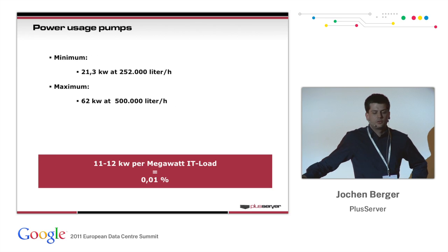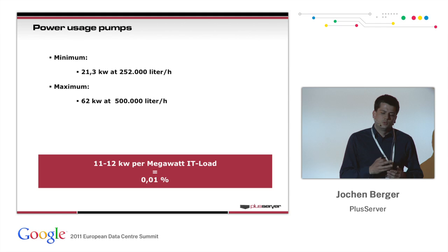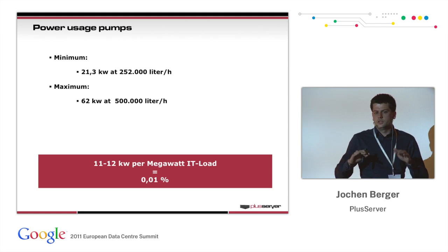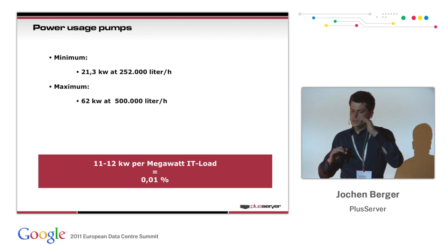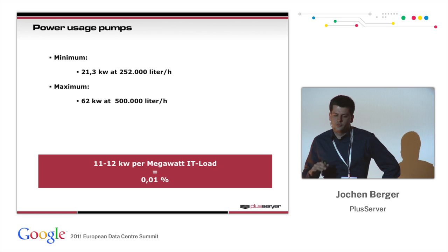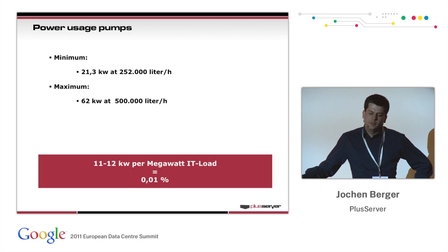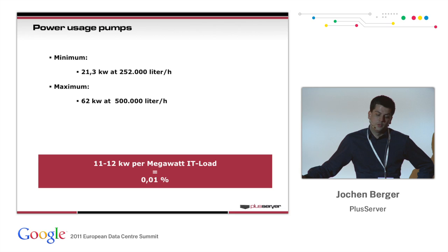Some numbers about the power usage of the pumps so that you get a feeling how much power it takes to pump that amount of water. Depending on how many liters, 250,000 is the minimum we can draw with the pumps because they just have certain specifications where they can run. With 250,000 liters, we're taking around 21 kilowatts. At 500,000 liters, it's around 62. So we are around 11 to 12 kilowatts per megawatt IT load, which adds to a PUE of just 0.01%, for the power usage of the pumps.